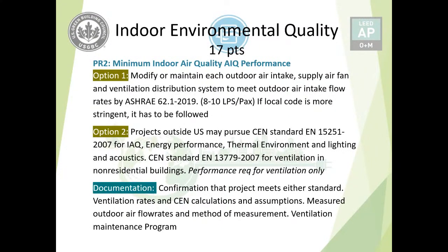Documentation for Case 1 includes confirmation that the project meets one of the standards, ventilation rates and calculations, any assumptions, compliance with 8 to 10 liters per second per person minimum for Option 1, major outdoor airflow rates and measurement methods, and a ventilation maintenance program to ensure the outdoor airflow rate does not fall below the requirement in the future.